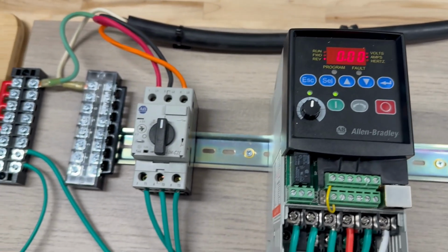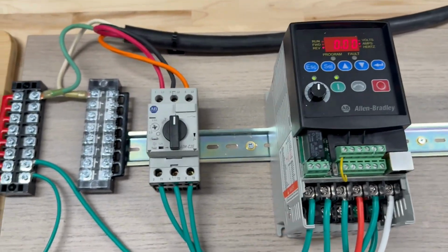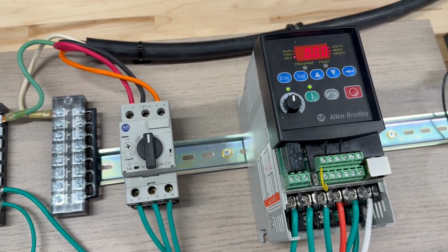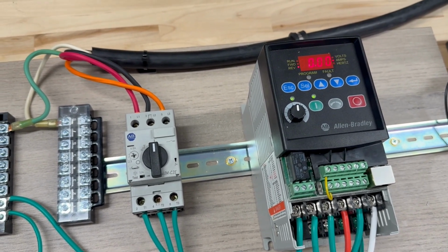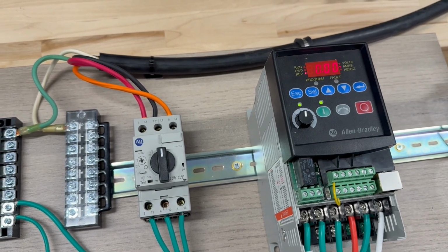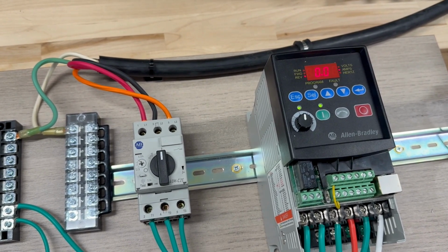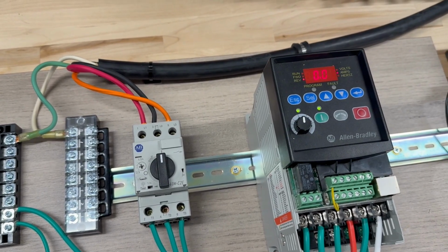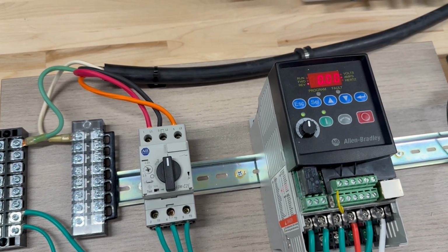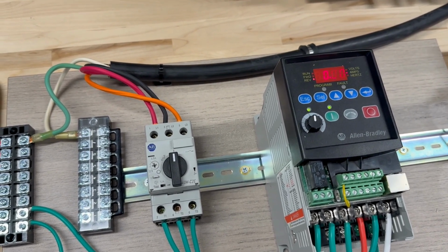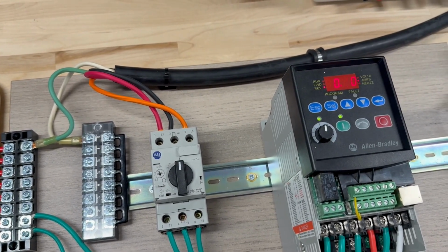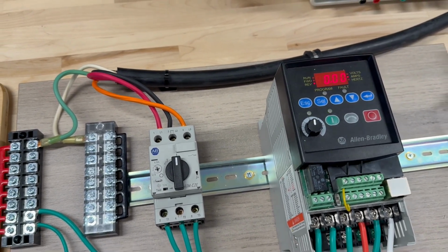One other thing that you could check, and I also mentioned that before, you could change the stop mode to the ramp, and whenever you have a non-zero value in A79, A80 and 81, it still does the same thing. Let's try that.